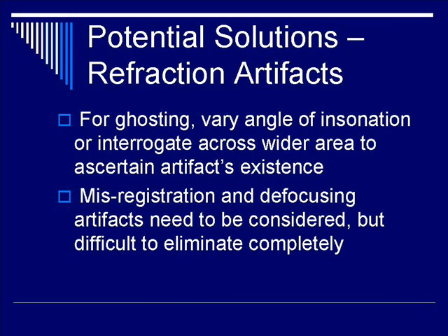To minimize or eliminate ghosting, you can vary the angle of insonation of the transducer, or interrogate across a wider area so you can see the artifact come in and out of existence — confirming it is an artifact and not an anatomical anomaly. Misregistration and defocusing artifacts also need to be considered; typically they're not as serious, but they are also difficult to eliminate completely with these techniques.